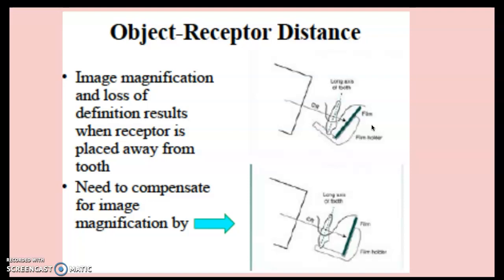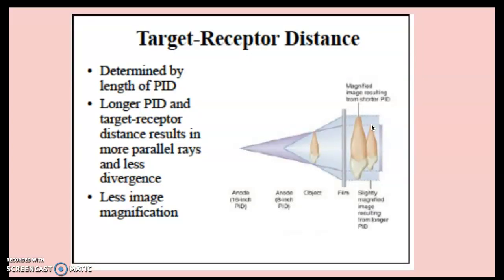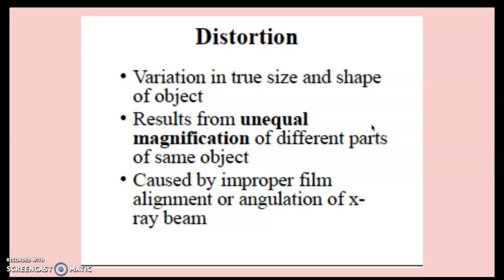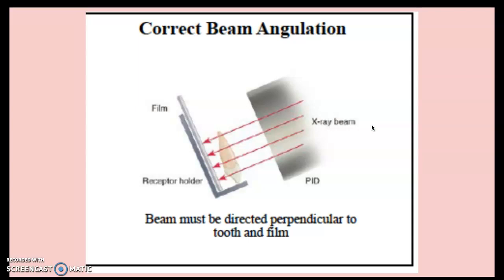You compensate for image magnification by increasing the target-receptor distance — the distance between the source, the target, and the receptor — as determined by the length of the PID. A longer PID and greater target-receptor distance results in more parallel and less divergent X-rays, producing less image magnification. Distortion is the variation in true size and shape, resulting from unequal magnification of different parts of the same object. It's caused by improper film alignment and angulation of the beam. The object-receptor alignment must be parallel to avoid angular relationships and distortion, and the beam must be perpendicular to both the tooth and the film.